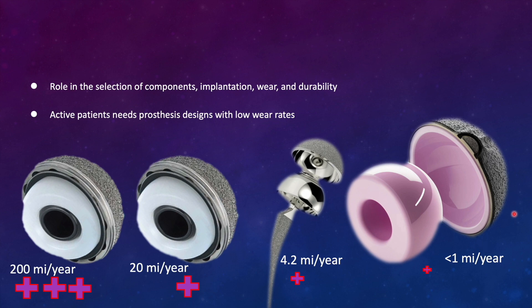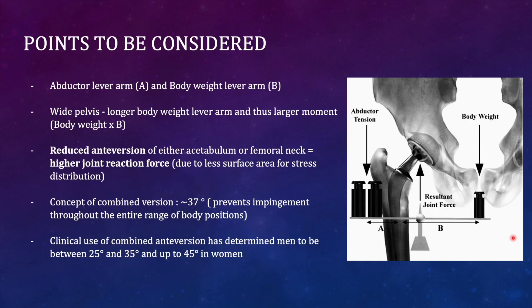Even though the debris is small, metal ions can result in metallosis, causing local tissue reactions and ultimately aseptic loosening of the components. The newer components widely used are ceramic ones — they have self-polishing properties, meaning they are scratch-resistant, and the wear rate is almost negligible, less than one micron per year. Therefore, in younger patients ceramic components are preferred. However, ceramic components are considered brittle, meaning they carry a risk of fracture.